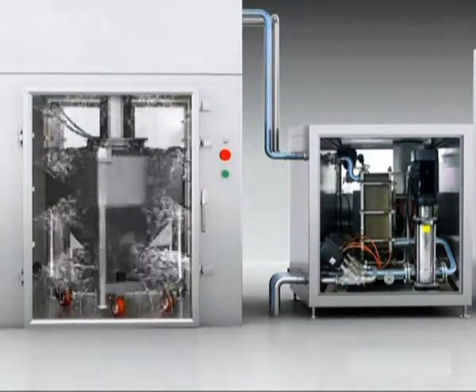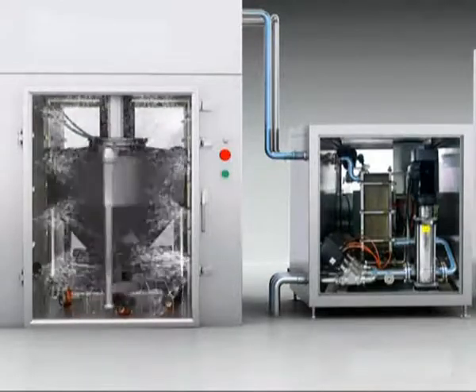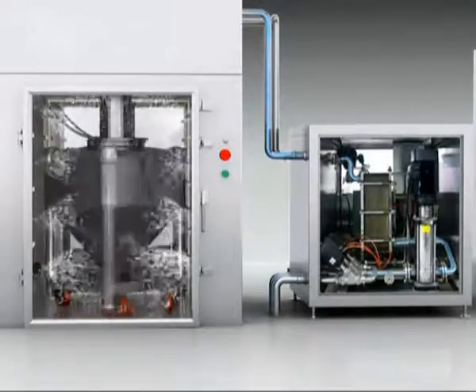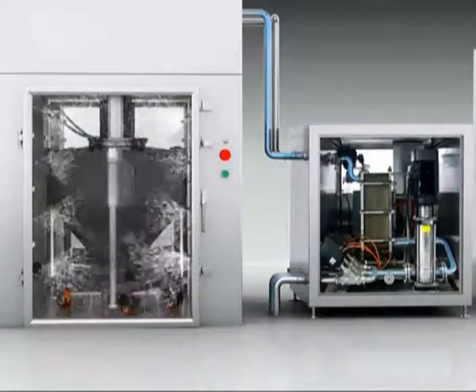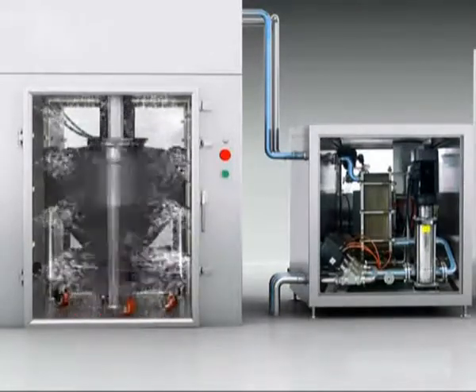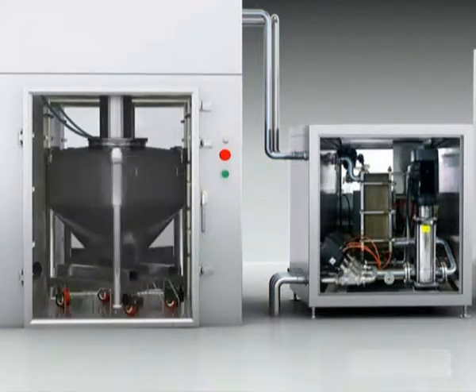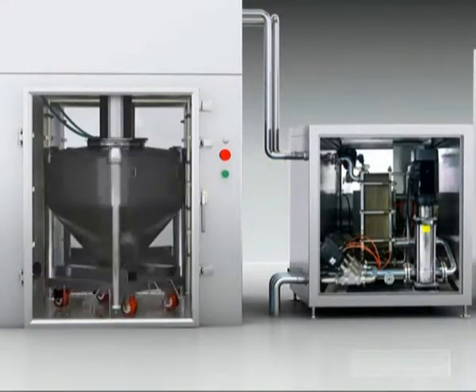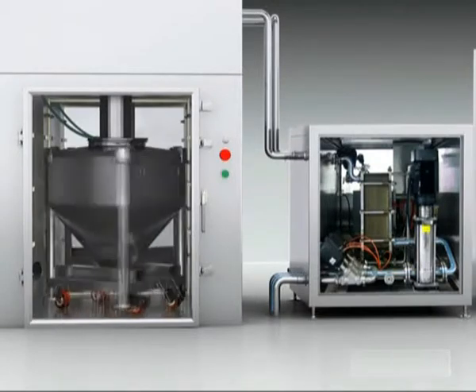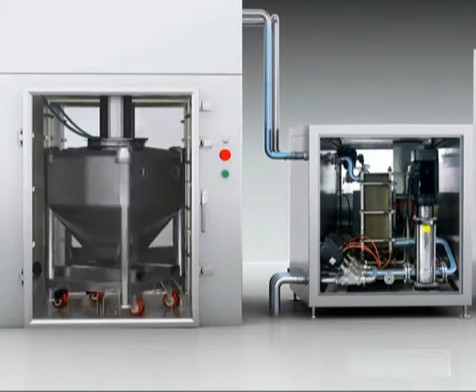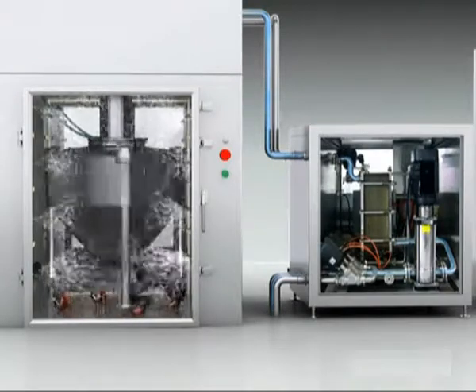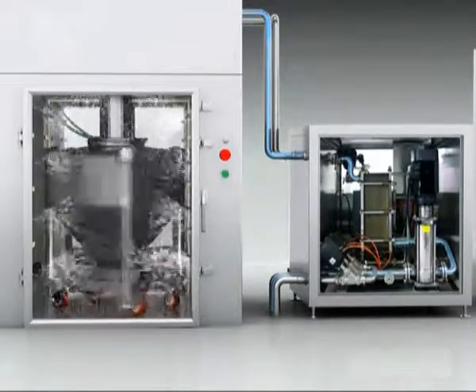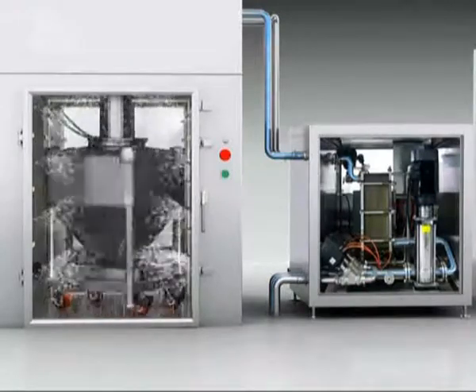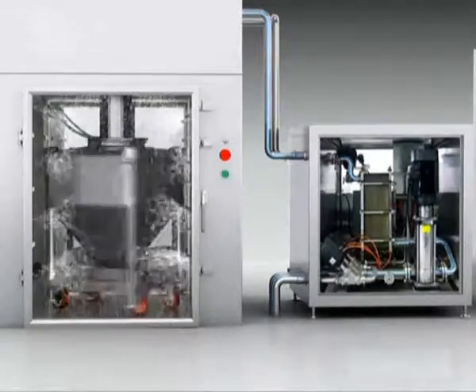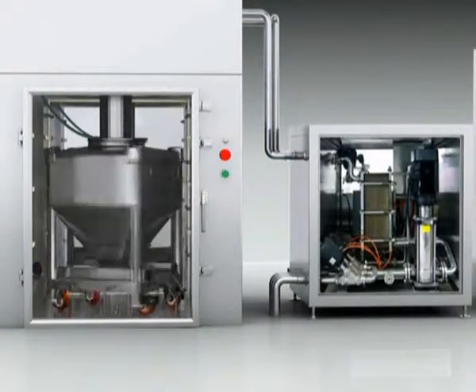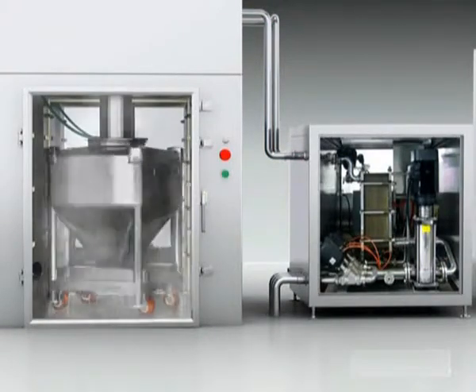After the detergent washing cycle is finished, pure water washing runs as the final cleaning cycle. The pure water pressure is raised by the boost pump inside the pump station and flows through the piping to the top washing board and the nozzles on the washing chamber walls for bin internal and external surfaces final cleaning. When the washing is finished, the system loads automatically the compressed air blow procedure. It blows out the remaining pure water inside the pipes. Upon finishing the compressed air blow, the drying cycle starts automatically.